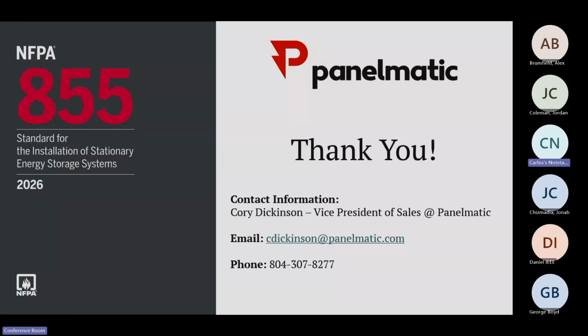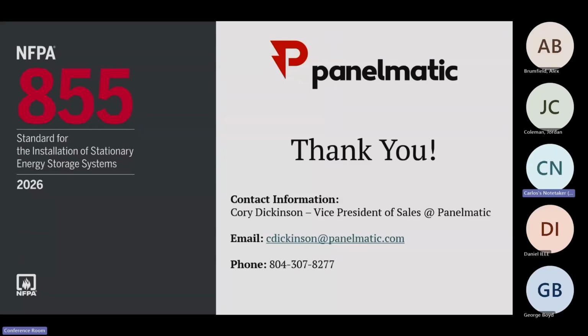So do they have to put in a monitoring system that might not even detect that? They're saying 2.5% based on the volume of the room is where airflow has to start moving. At 5%, you have to prove recirculation within a certain time, but it all stays below 25% LFL, the lower flammable limit. We've seen it set at 5% of the volumetric space, with a gas detector set point at 2.5% to alarm and say start moving air.